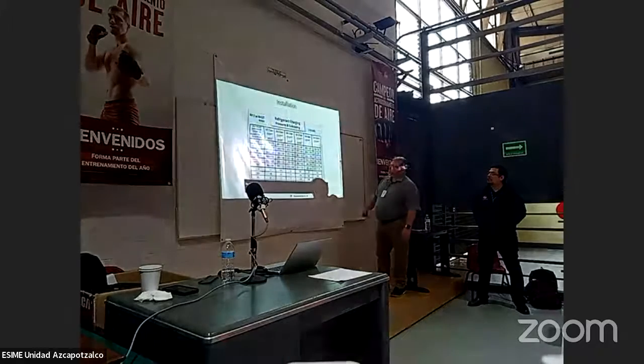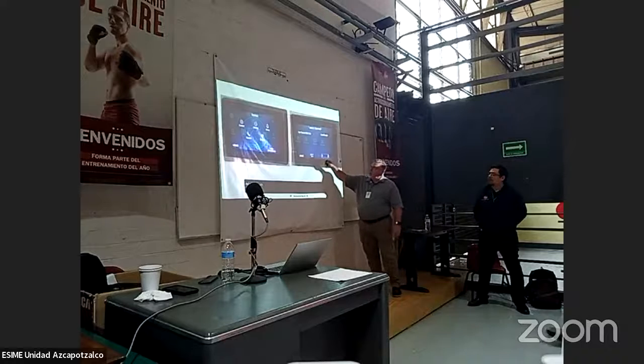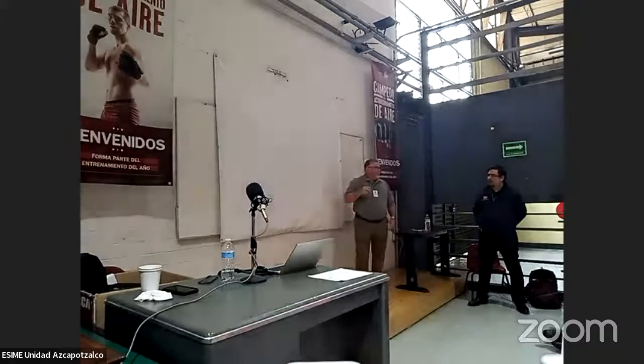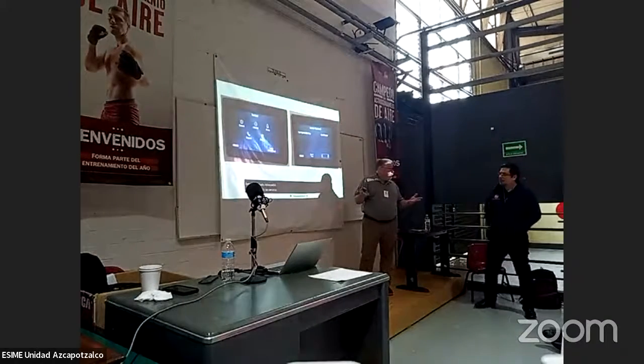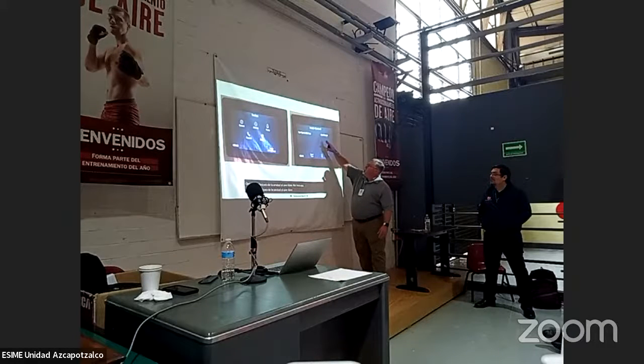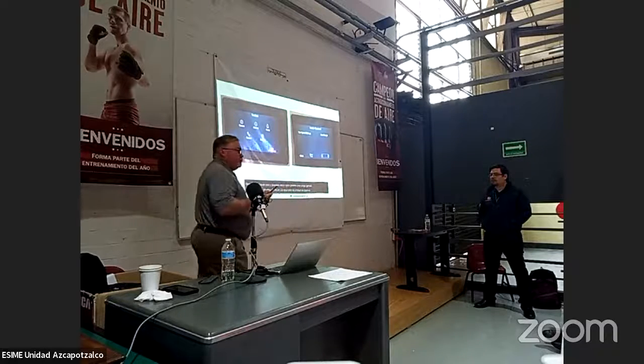So you click service, okay? Oh, wait a minute, it went backwards. There we go. Click service. Then you're going to come here. You'll see outdoor unit checkout. Okay? You get the outdoor unit checkout. And then you're going to toggle this where you want cool charge or heat charge. Once you do that, say you want cool charge, you're going to hit start test. What that's going to do is ramp the system up to full speed. You're going to let that run for 30 minutes at full speed.